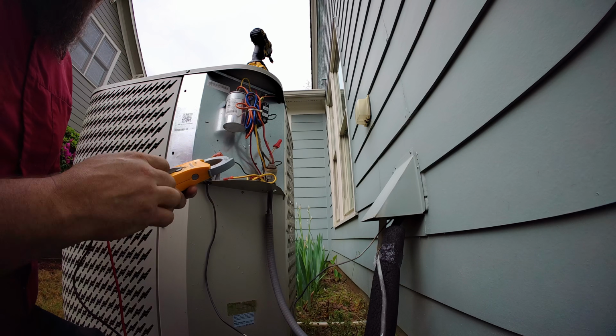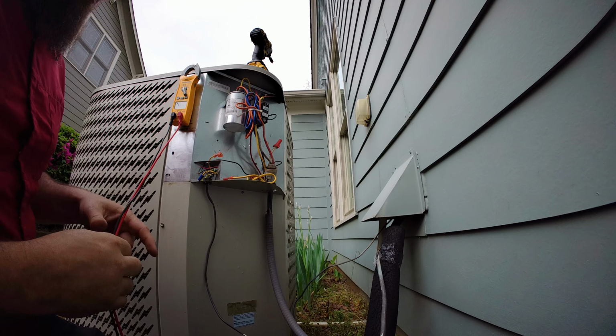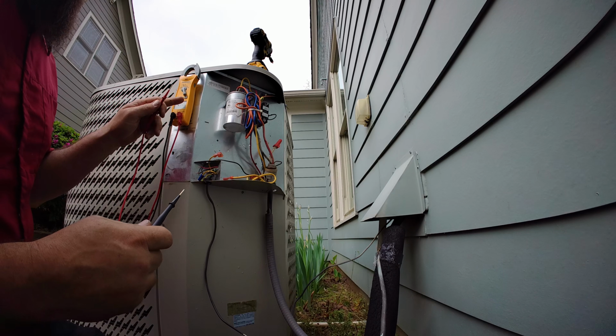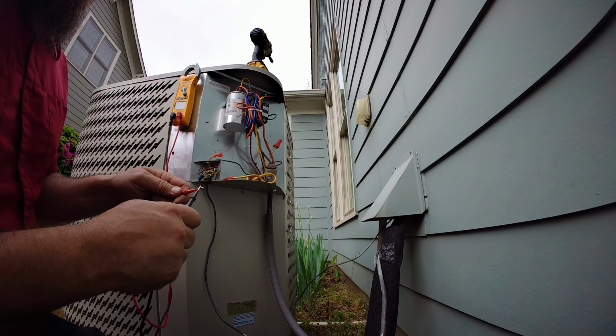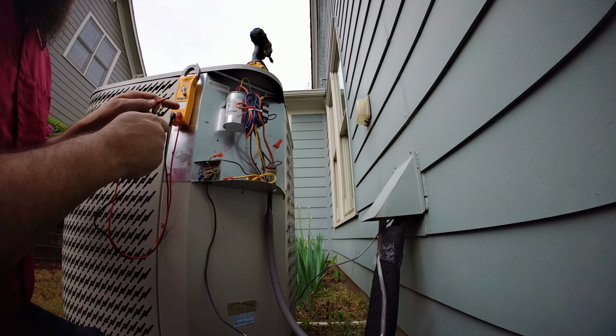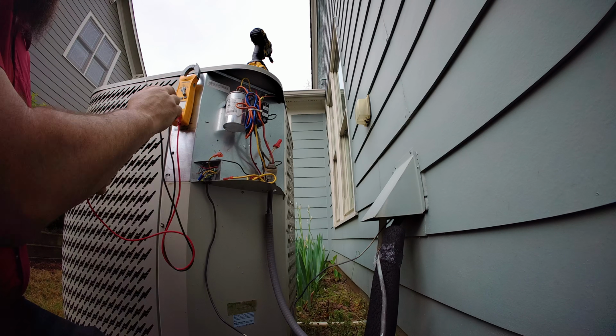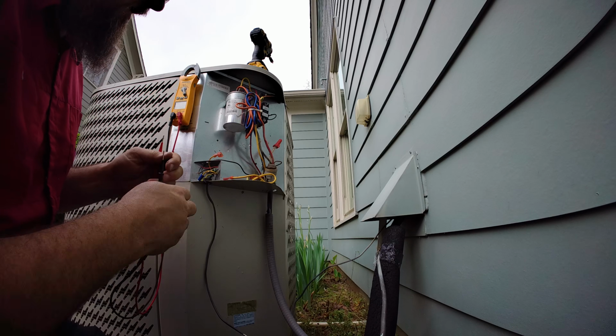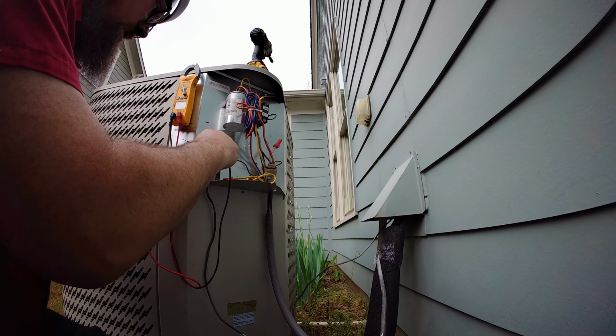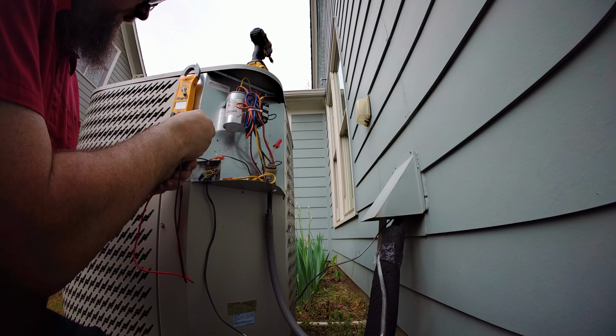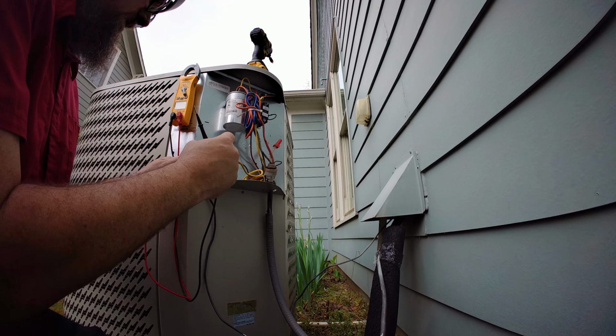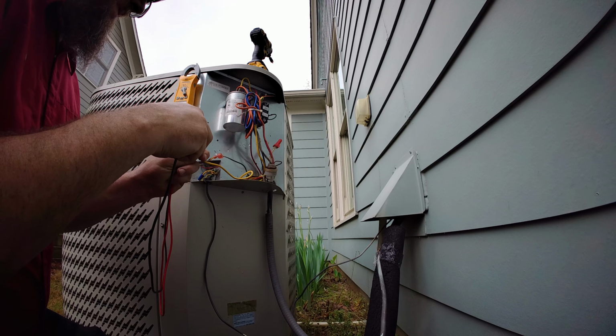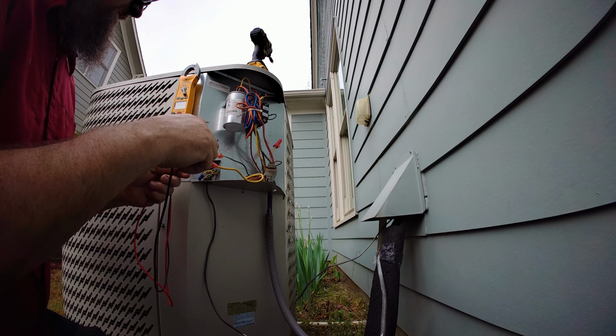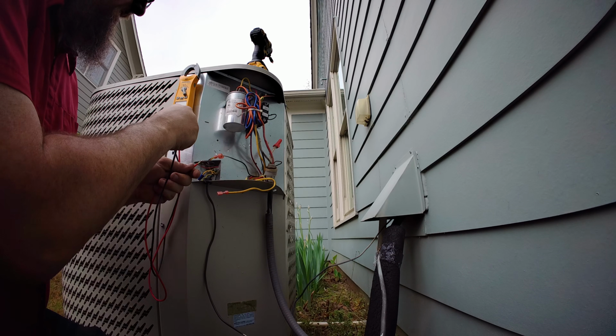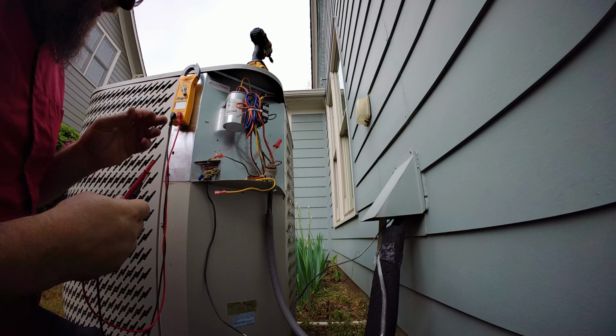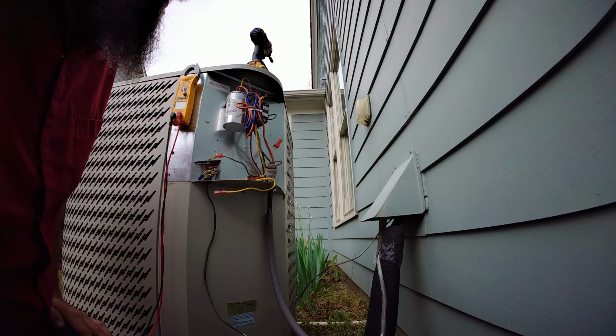And we'll just put our meter into continuity mode, so we should see either open load if nothing's connected, or tone, and it will give us an actual ohm reading there to know how we're shorted. So we'll check between one of these and ground. We've got nothing. So I think we're good as far as any kind of electrical short.